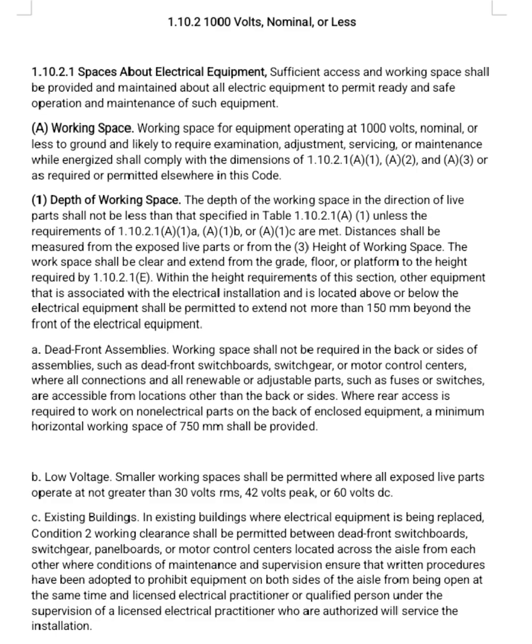B. Low voltage. Smaller working spaces shall be permitted where all exposed live parts operate at not greater than 30 volts rms, 42 volts peak, or 60 volts DC. C. Existing buildings. In existing buildings where electrical equipment is being replaced, a Condition 2 working clearance shall be permitted between dead front switchboards, switchgear, panelboards, or motor control centers located across the aisles from each other where conditions of maintenance and supervision ensure that written procedures have been adopted to prohibit equipment on both sides of the aisles from being opened at the same time.